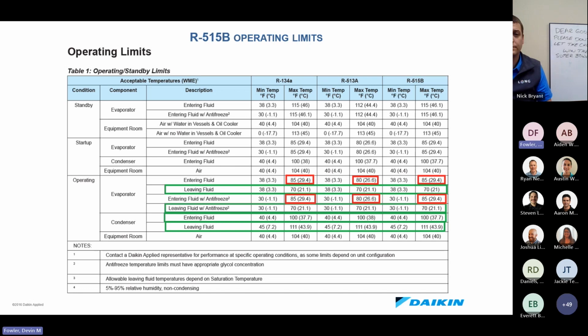Our operating limits, however, do not change. We're able to keep the same entering evaporator and condenser fluids, as well as the same leaving fluid temperatures that we would have with R134A. We can have up to 85-degree water entering our evaporator and up to 70-degree water leaving our evaporator. On the condenser side, we can have up to 100-degree water entering the condenser, and we can leave out as high as 111 degrees. None of that's going to change with the new refrigerant. We can keep everything pretty much the same if we are doing a retrofit. You don't have to worry about changing your towers or changing your flows on your equipment in order to stay within these temperature limits.